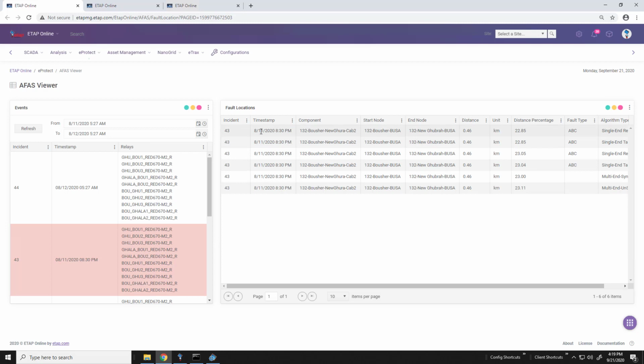So here in the fault location section associated with incident 43, we can see a number of different calculations for that fault, as we use different algorithms. Here we can see a number of different algorithms: single end reactance, single end Takagi, etc. We can use that information to get a very precise estimate of where the fault is located. So for instance, this fault started at this node, ended at this node, and was on this cable at roughly 0.46 kilometers away. You can see each of these different calculations has roughly the same value, but if we use multi-end, we have a very accurate location, about 23% down the line.